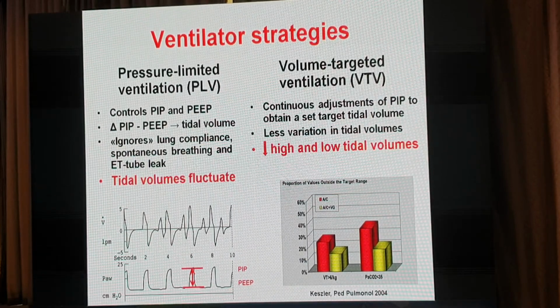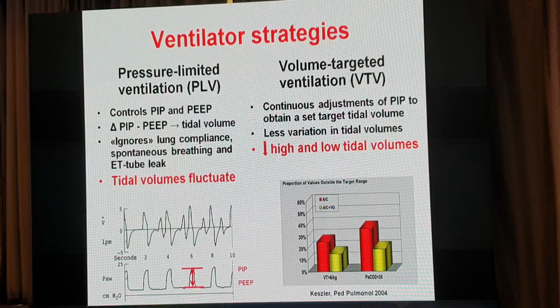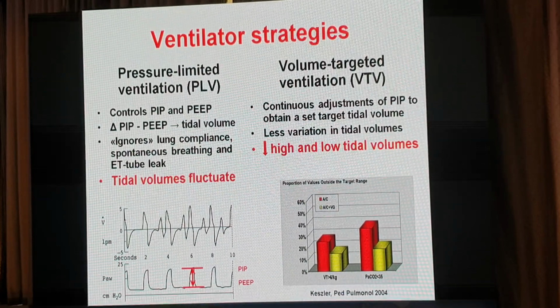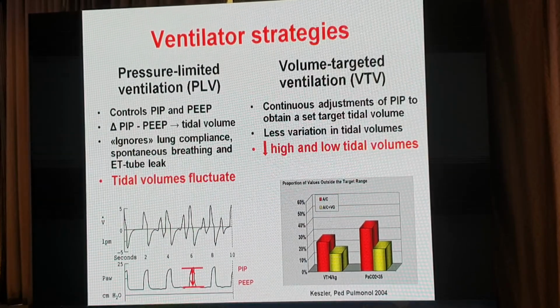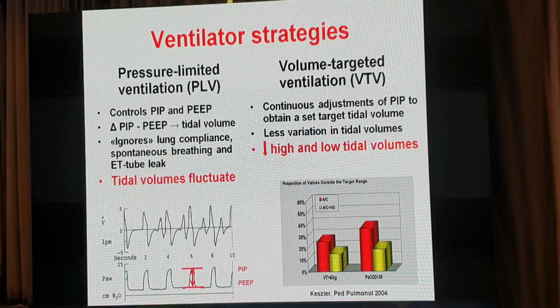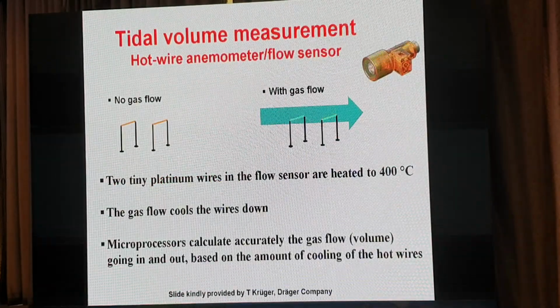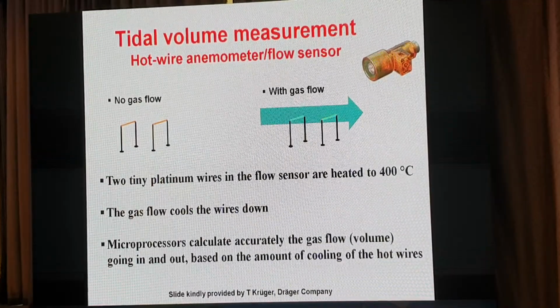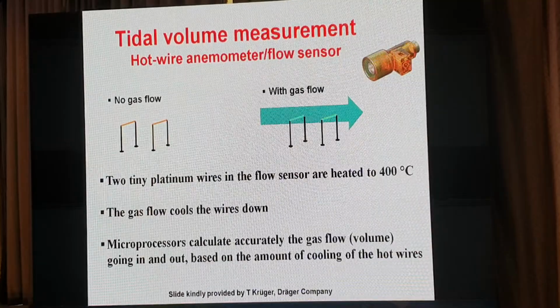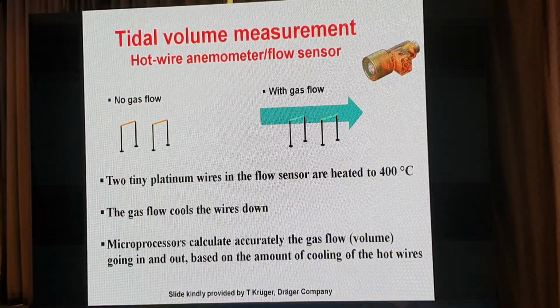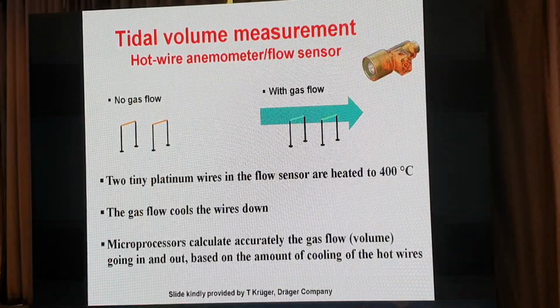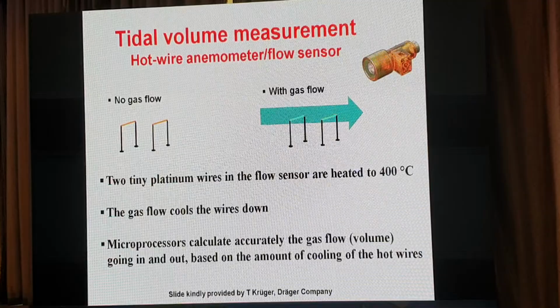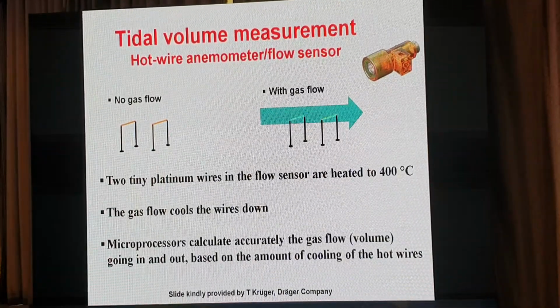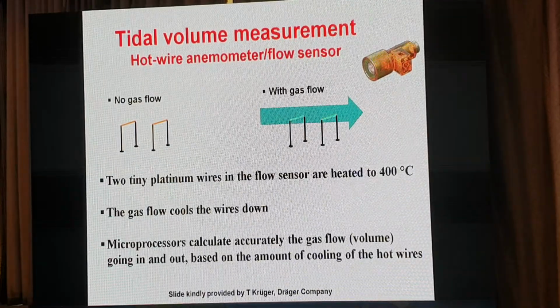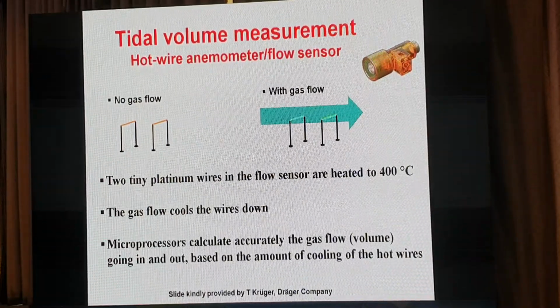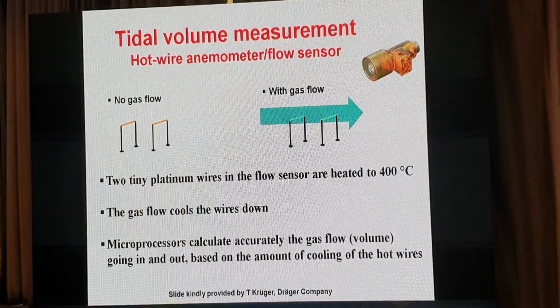This has been shown in several different studies, but Martin Keszler, a famous American professor, showed this many years ago: you have much less high tidal volume and much less low tidal volume by using this approach of volume-targeted ventilation. The basic principle to be able to do this is that you can have very accurate tidal volume measurements with the modern flow sensors, the hot wire anemometer flow sensors, where you have 2 tiny platinum wires. It's quite fantastic how this works. These tiny wires are heated to 400 degrees Celsius, and then the gas flow passing across them cools the wires down, and this can be used to measure the gas flow passing the 2 wires. They can even calculate the direction of the flow over these 2 wires.